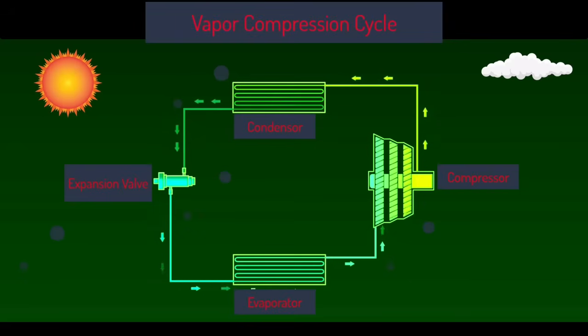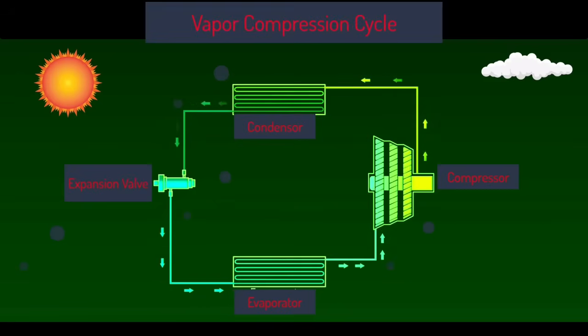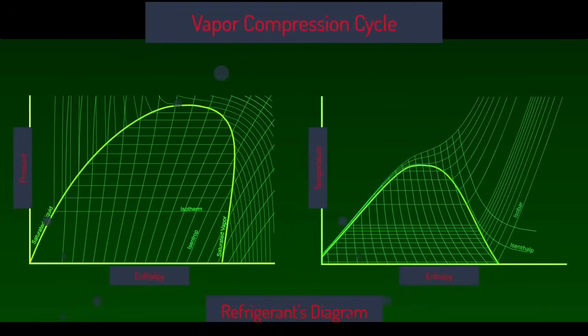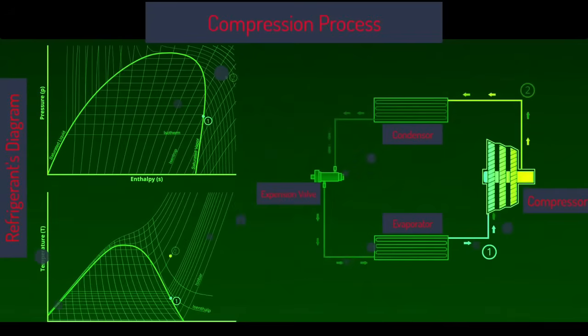The cycle has 4 key thermodynamic processes, and we'll walk through each one using pressure enthalpy and temperature entropy diagrams to visualize energy transfer. From point 1 to 2, the refrigerant enters the compressor as a low-pressure, low-temperature saturated vapor. The compressor performs isentropic compression, raising the pressure and temperature significantly. At point 2, the refrigerant is a high-pressure, high-temperature superheated vapor.